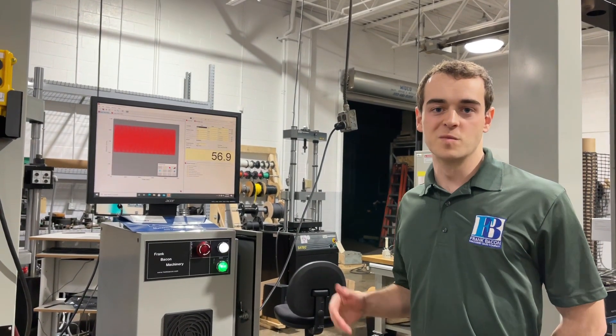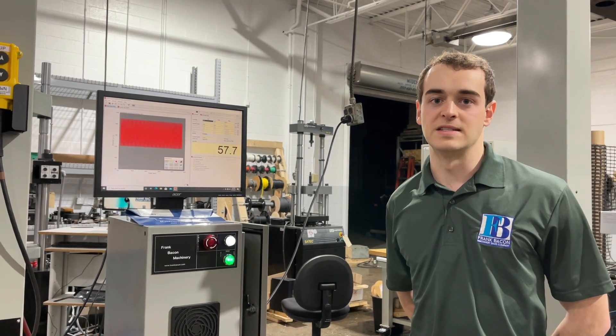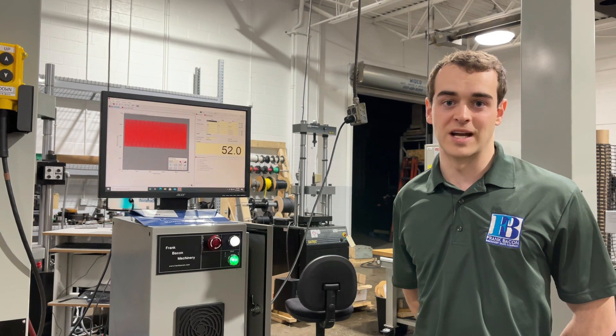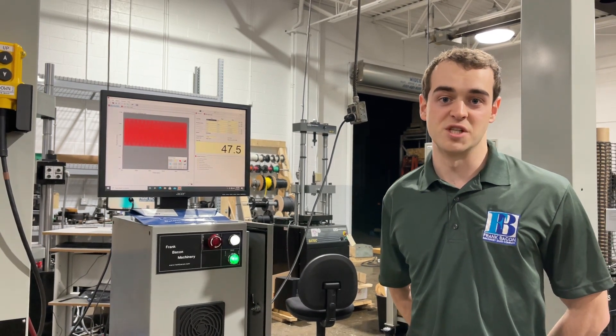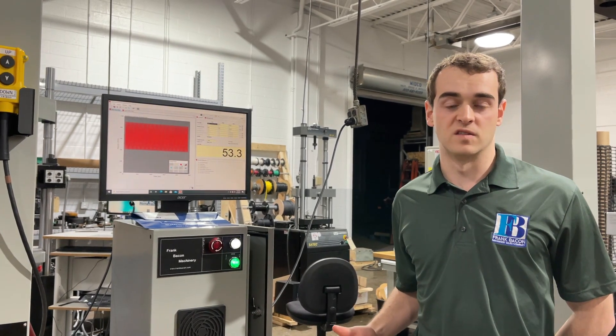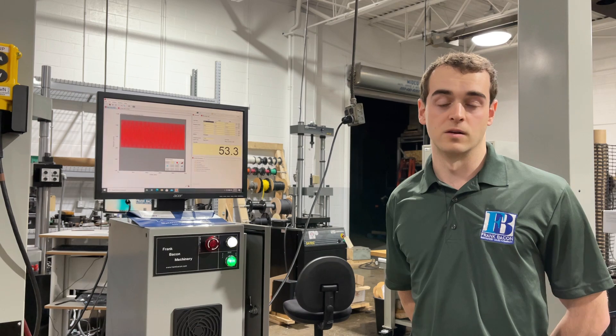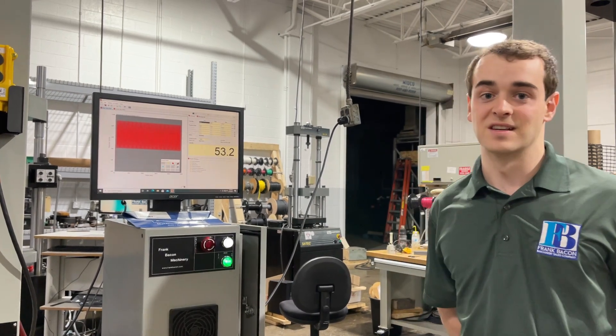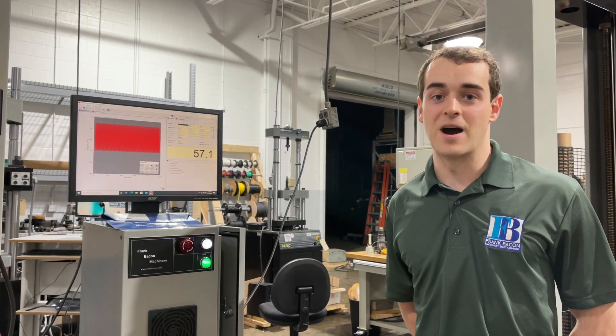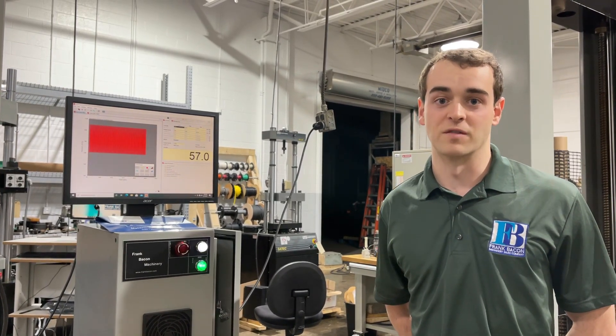With this machine running a cyclic test that's kind of high frequency for a tensile testing system, we did want to make sure that this customer got an elite machine. The new Yaskawa drive and motor was imperative for great control as well as speed. This machine can run at about 60 inches a minute, which is pretty quick for one of these units.